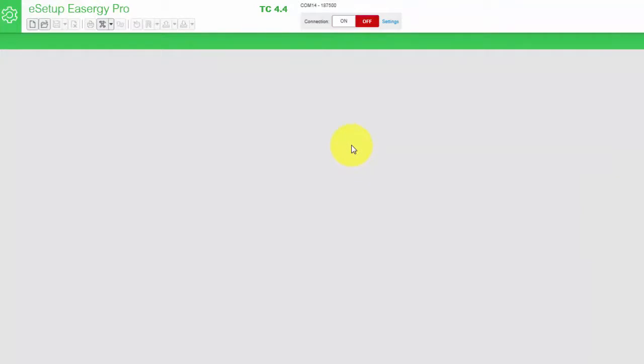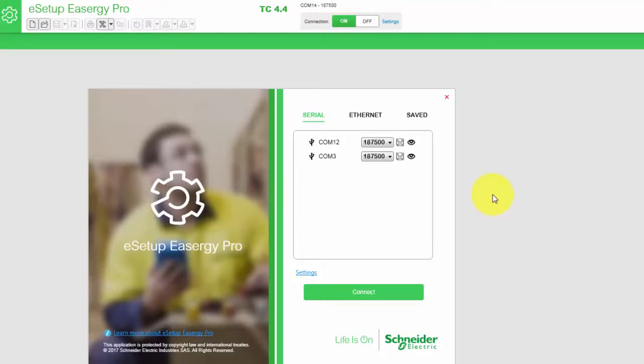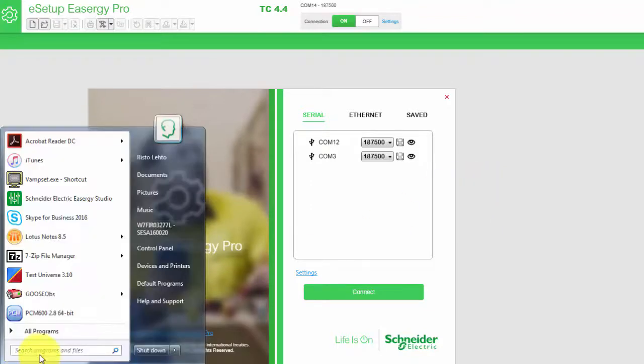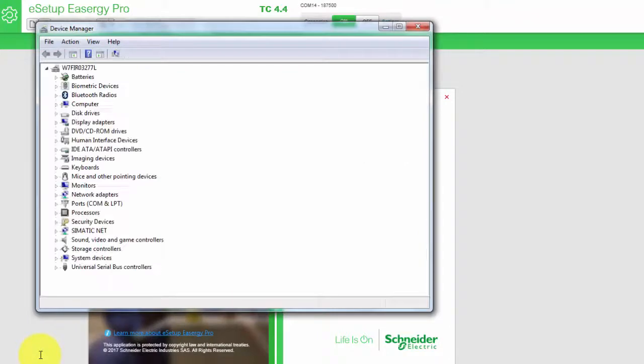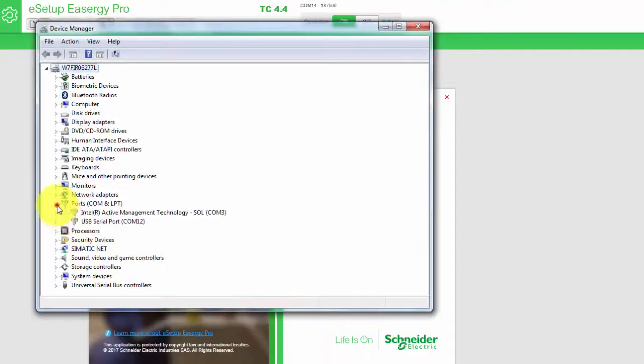To establish the connection after we have connected the cable to the front port, we press on 'Connection On'. Easergy Pro will provide us with a list of COM ports which are available in Windows. In order to know which COM port is connected to the relay, we can check by typing 'Device Manager' into the Windows search and look under Ports, COMs and LPTs.